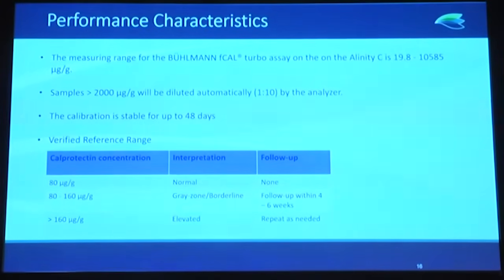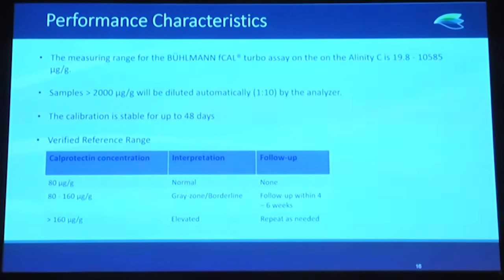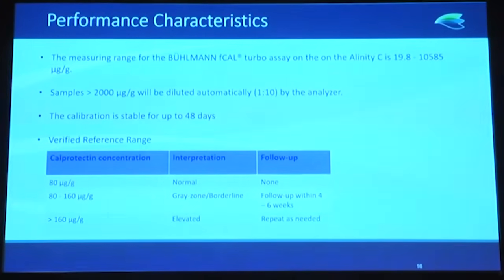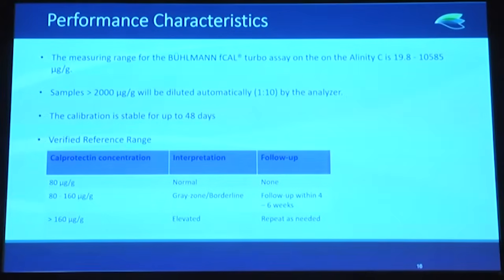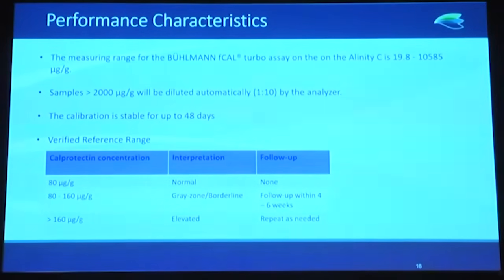The performance characteristics on the Alinity C platform show a measuring range of approximately 19.8 up to 10,585 micrograms per gram. Samples are diluted automatically 1-in-10 for values above 2,000 micrograms per gram. Calibration is stable up to 48 days, and we have verified a reference range with a cutoff at 160 micrograms per gram and above.